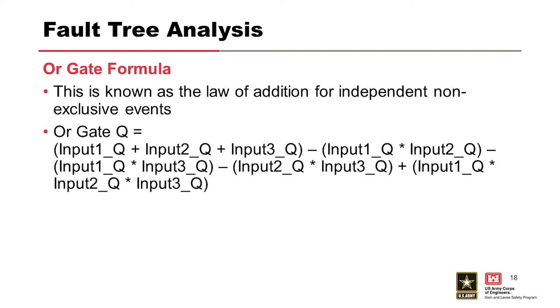And so the OR gate formula is an example shown below. The OR gate is known as the law of addition for independent, non-exclusive events. And again, for an example, OR gate formula is shown here with, gate fails to operate. That could be due to gate operation controls failed, gate mechanical drive fails, or electrical power source fails. And that formula at the top there is the mathematics that would go along with that OR gate.